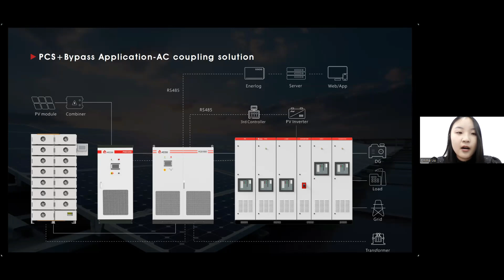Another main issue about this kind of large-scale systems is the high ratio of inductive loads. Here are some pictures of the potato farm project we have done in South Africa. There are water pumps and heavy machines for packaging. The inductive load power reached even 70%. The problem is that when the inductive load ratio is that high, when the grid is off, the PCS needs to switch to off-grid working mode. AC output fluctuations caused by switching can endanger the system's stability.